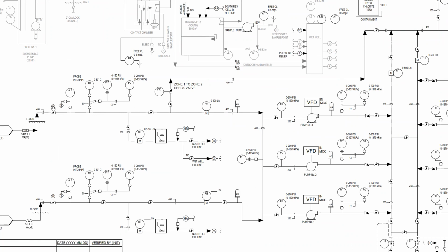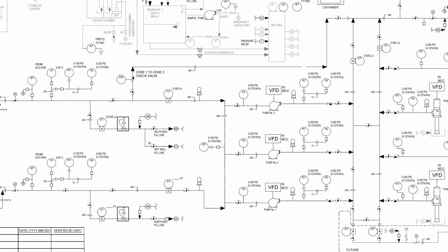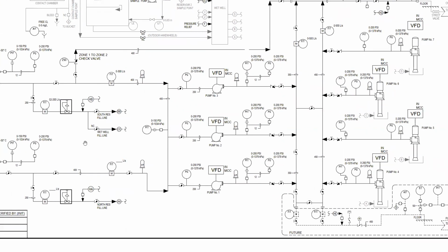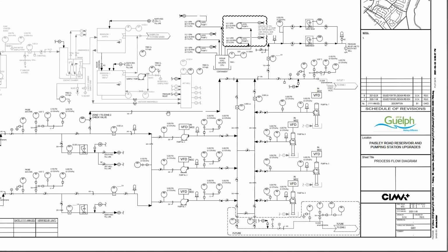So we've got 400 mil pipe into a manual valve, into what is going to be a chlorine analyzer, a temperature probe, and pressure. It branches off into a flow meter to fill reservoirs. We've got, again, chlorine analyzer, temperature, pressure. And this is the north fill reservoir line with a flow meter. We've got two other flow meters to our pumps 1, 2, and 3 that will boost pressure into the other zones. We've got pumps 4, 5, and 6, which take water out of the reservoirs and will boost water into zone 2. We've got up here sodium hypochlorite. We dose hypo into the water for disinfection.